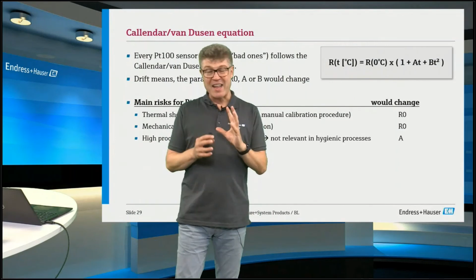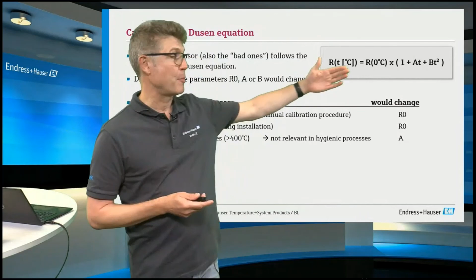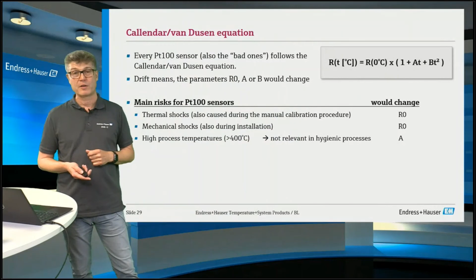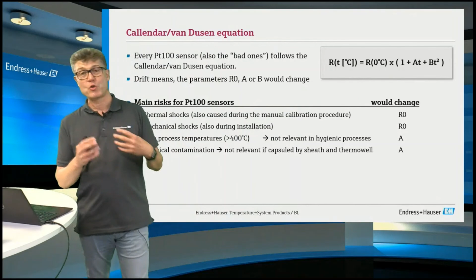Because it is platinum, and platinum as a metal comes in so-called grains, so small crystals, and at high temperatures the grains start to grow, they connect to each other, and this can change the material structure and change the factor A. This, according to literature and our results, happens at temperatures higher than 400 degrees. The TrustSens is limited to 160 degrees, so it is not exposed to 400 degrees, it cannot happen. And the next one, even less likely, chemical contamination of the platinum sensor itself.